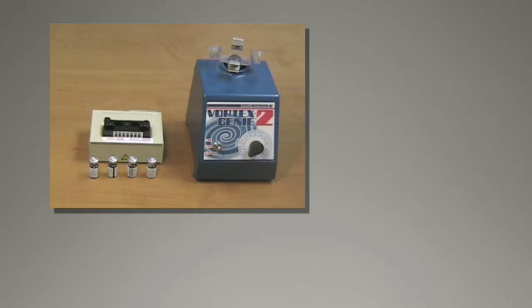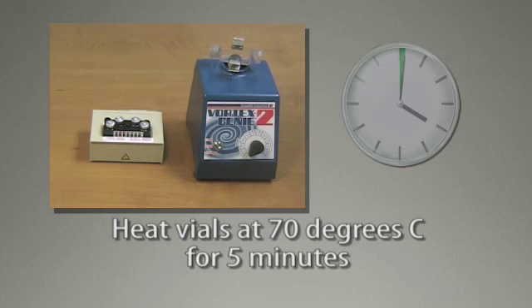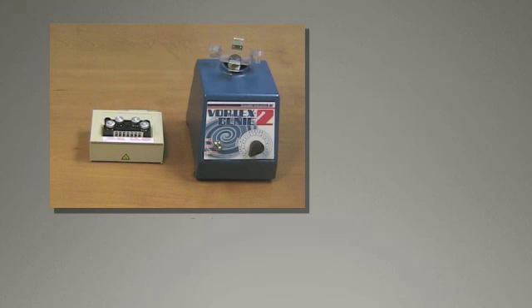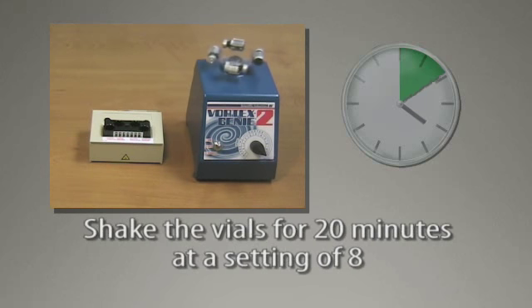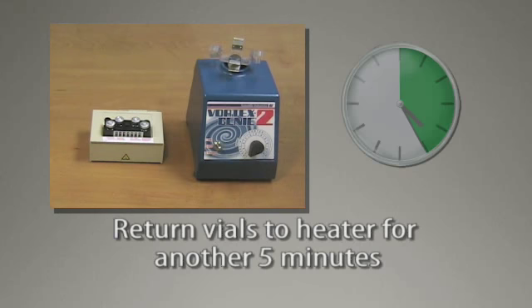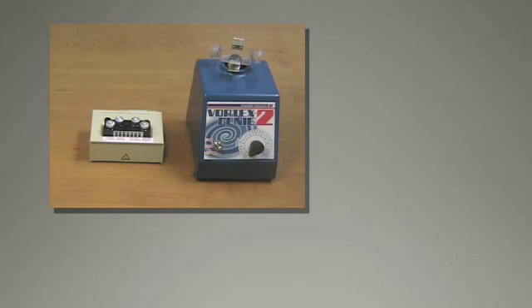Prior to injecting Onyx, load the Onyx heater with 4 vials of Onyx and heat the vials at the preset 70 degrees Celsius for 5 minutes. After heating, shake the Onyx vials for 20 minutes at a setting of 8, then return the vials to the heater for another 5 minutes. Allow the vials to remain in the heating block until use. Any unused vials can be returned to their original packaging.